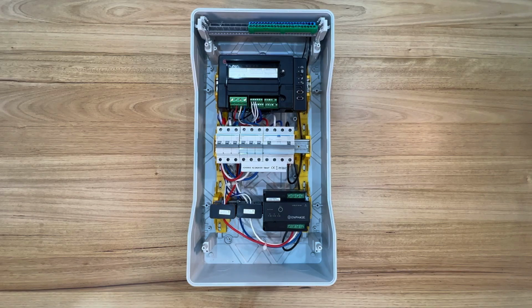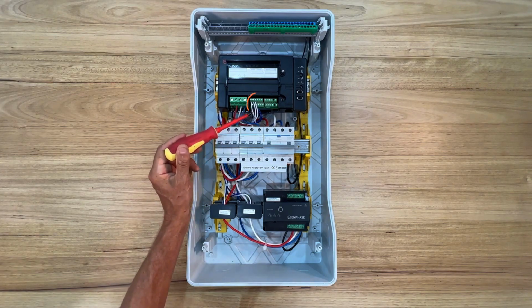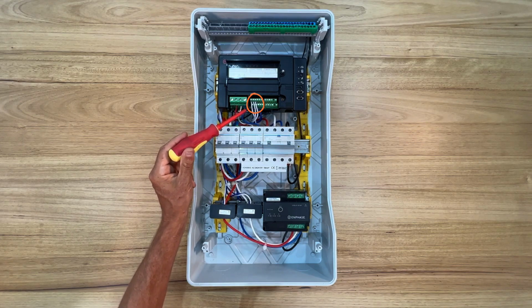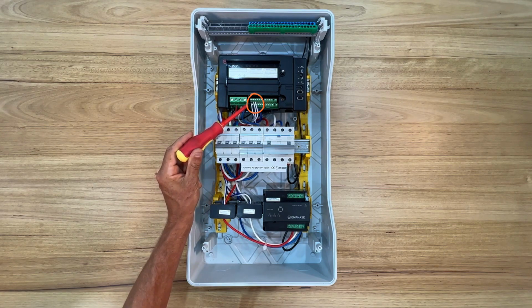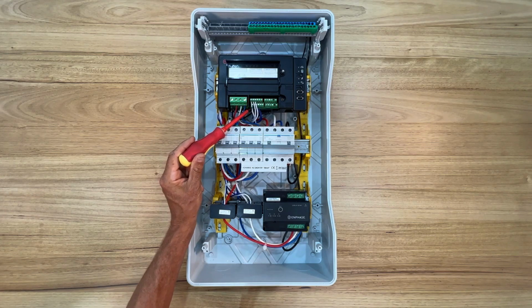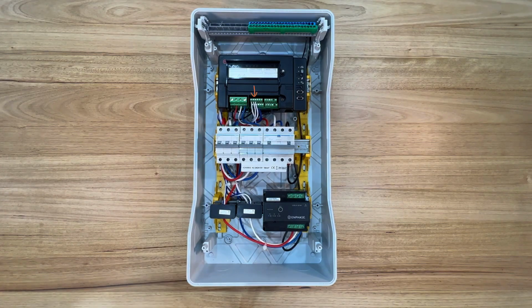Now white and blue phases, or line 2 and line 3, must also correspond correctly across the installation. And for each CT, the white conductor goes to the top row at the CT terminal of the IQ gateway, and the blue conductor always goes to the bottom row. The first 3 connections are for the solar production, then the next 3 connections on the terminal block are for consumption metering. Now always confirm you have wired into the correct terminals here.